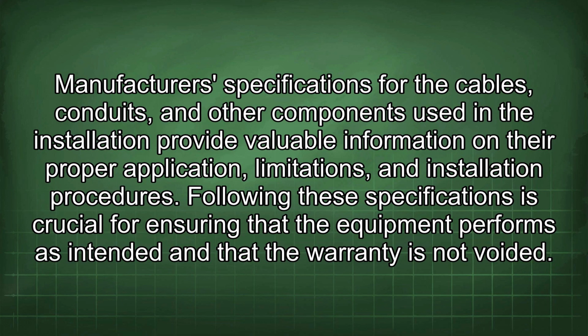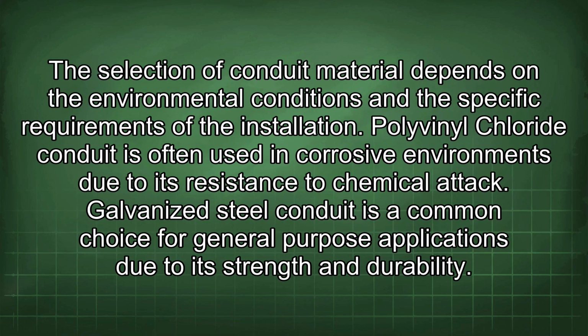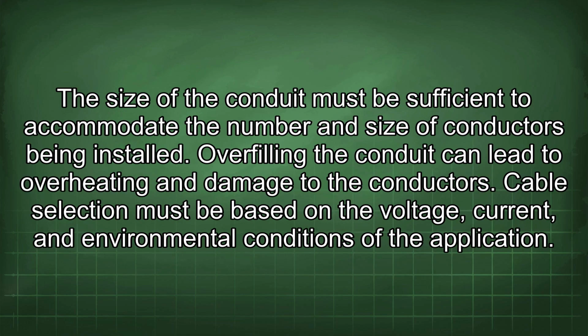Following these specifications is crucial for ensuring that the equipment performs as intended and that the warranty is not voided. The selection of conduit material depends on the environmental conditions and the specific requirements of the installation. Polyvinyl chloride conduit is often used in corrosive environments due to its resistance to chemical attack. Galvanized steel conduit is a common choice for general-purpose applications due to its strength and durability. The size of the conduit must be sufficient to accommodate the number and size of conductors being installed. Overfilling the conduit can lead to overheating and damage to the conductors.